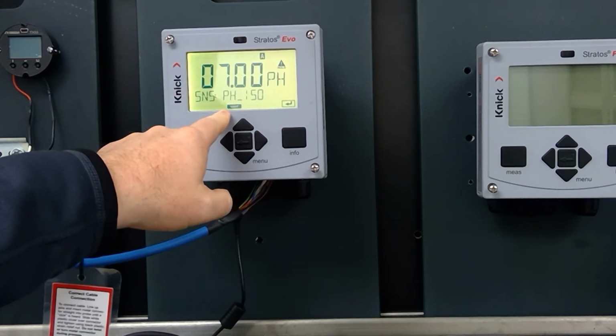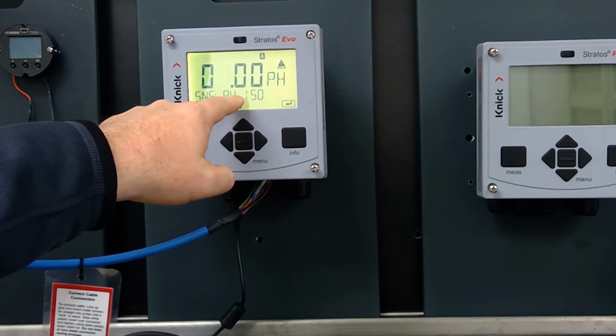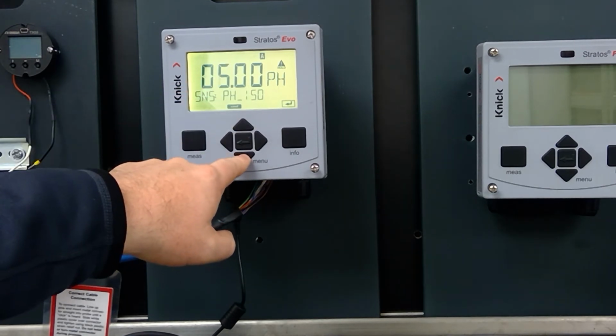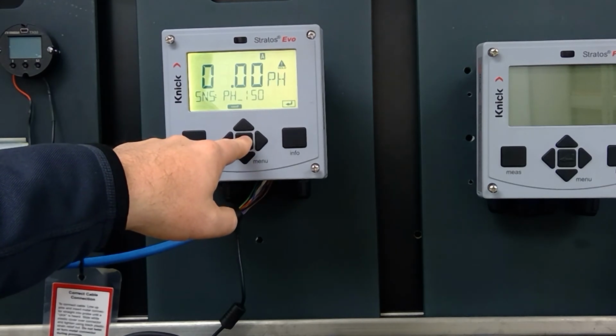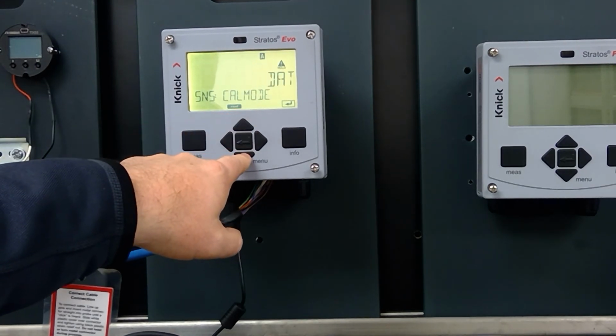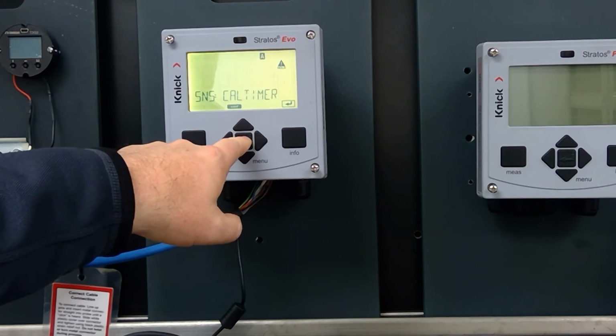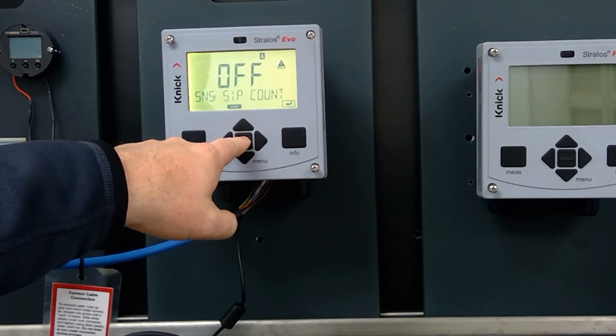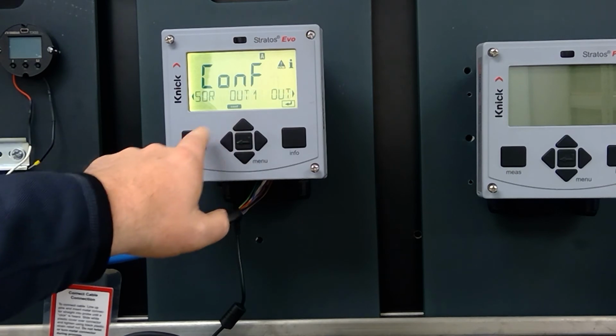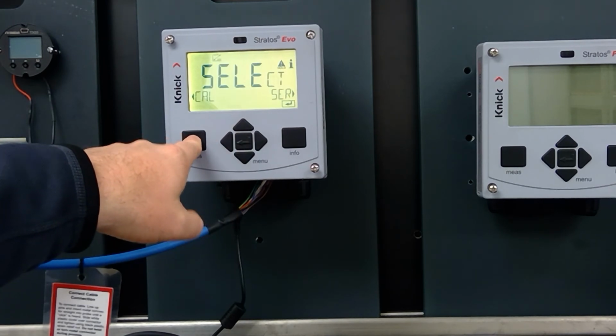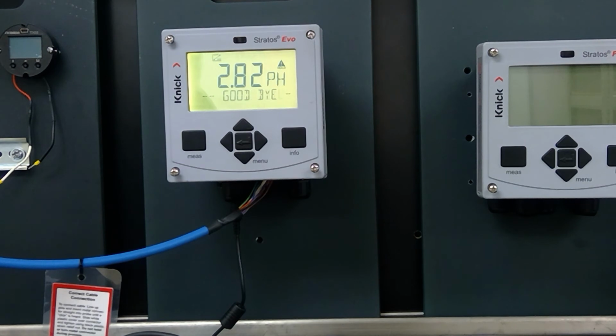Then for the Type 18 on one of our transmitters, the pH ISO is always going to be 3. So then you would put in 3. Cal mode, we're going to take it to manual. Cal timer off, CIP off, SIP off. And then you can go back to the measurement screen. Now at this point, don't be concerned if it's giving a very wrong pH measurement value, because we have not done the calibration of this sensor yet.